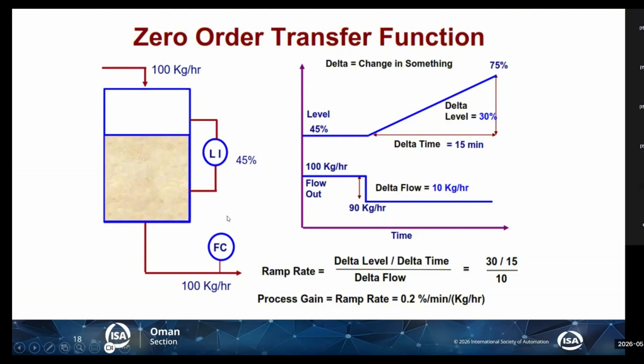So it doesn't have something called TTSS, time to steady state. It doesn't have steady state. It is an integrating system. It will just keep on increasing since you haven't adjusted the valve. And in this zero order transfer function, we don't have a process gain. We have something called ramp rate, which is the same as process gain, but we call it ramp rate.